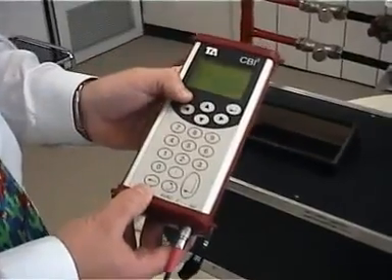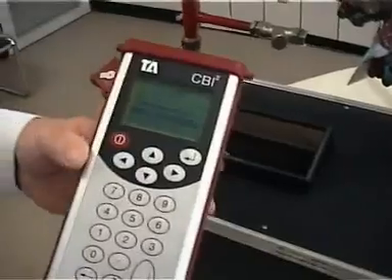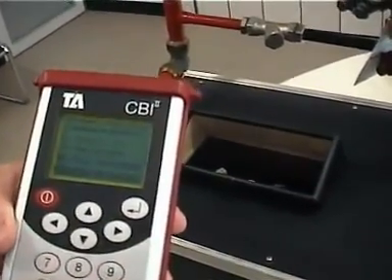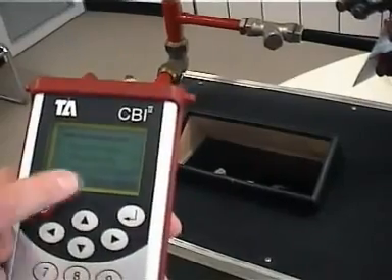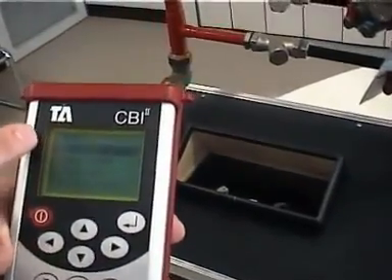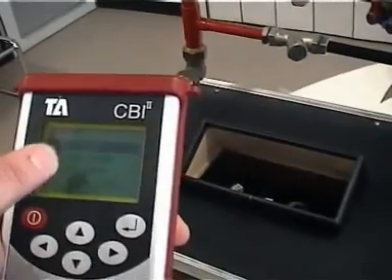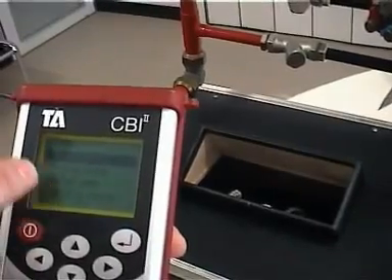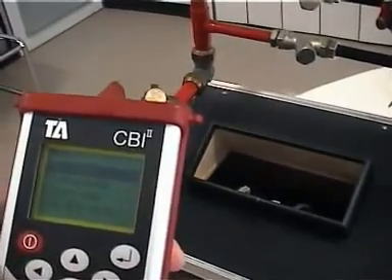On site, we've now arrived. Turn the machine back on. We choose the function that we're going to do, and we're going to do a TA balance today. We choose function number 4, which comes up with TA balance. We hit the enter key, and it tells us whether it's a new module, an existing module, if it has a partner valve, and if it's got a pressure drop. If we want to change the differential pressure or the partner valve, we go into it at this time and do it.